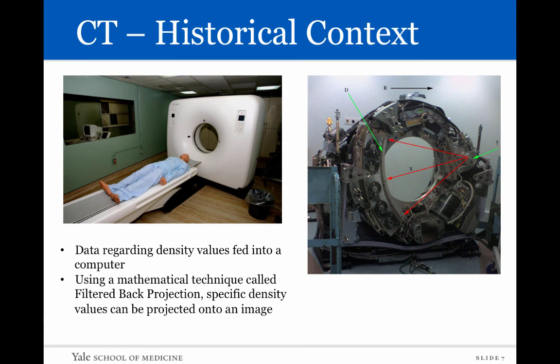The idea is that you have an x-ray source, similar to conventional radiography, placed at one end of a large circle. On the other end, there are a row of detectors. When the x-ray source is switched on, it releases x-rays that are detected by these detectors. For every slice it goes through, data regarding density values are fed into a computer. Utilizing a mathematical technique called filtered back projection, you can post-process this data and assign specific density values with different shades of gray going from black to white, which are then projected onto a computer screen to make up the image of that particular slice.